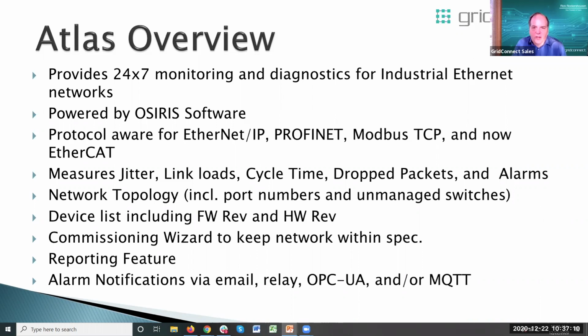There's also a commissioning wizard feature that uses the specs developed for Profinet by the PI organization, Profibus, Profinet International. The trade organization for Ethernet IP is called ODVA, Open DeviceNet Vendors Association. Those two organizations have standards about how Ethernet IP and Profinet networks should be designed and set up.